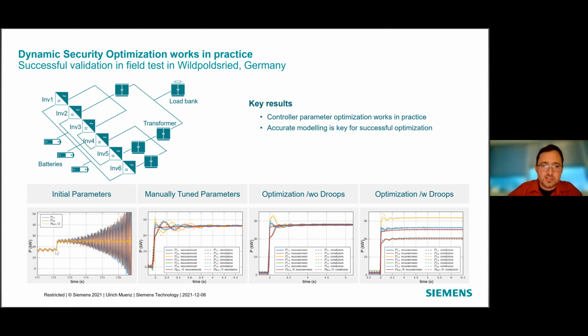Here you see measurements. The first one, on the left-hand side, is an initial set of parameters where only 2 of the 6 inverters are feeding into the load bank. There's a load step, and then they start oscillating against each other—obviously nothing you want to see in your system. We did a manual tuning of the parameters, spending quite some time on it, and then you see here a load step where the system is stable, which would be okay.